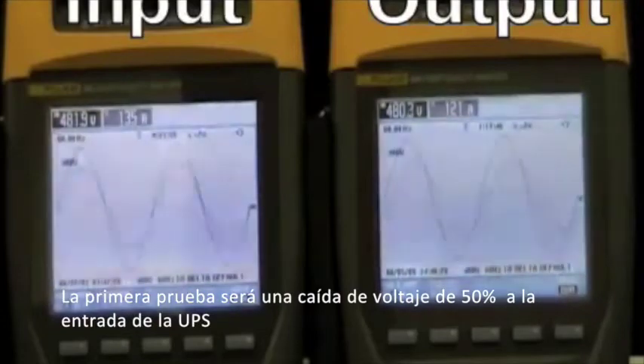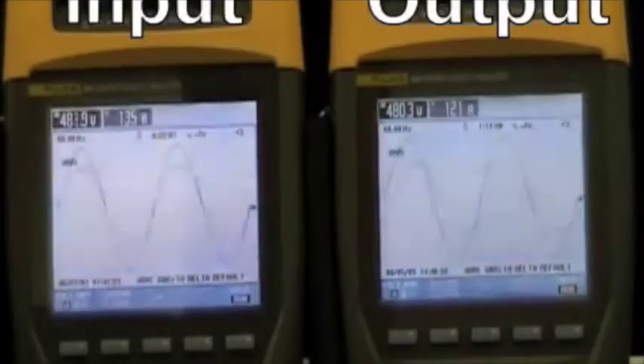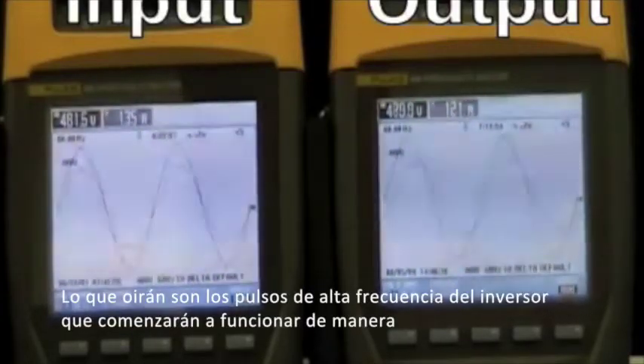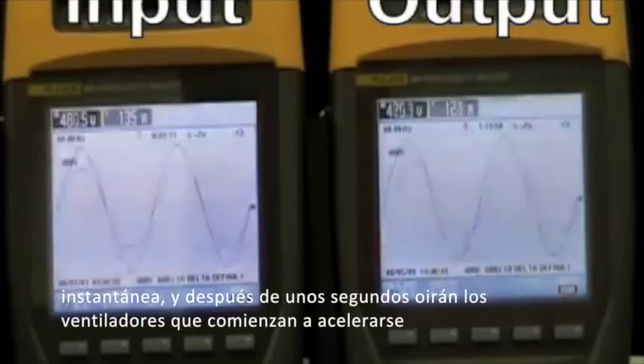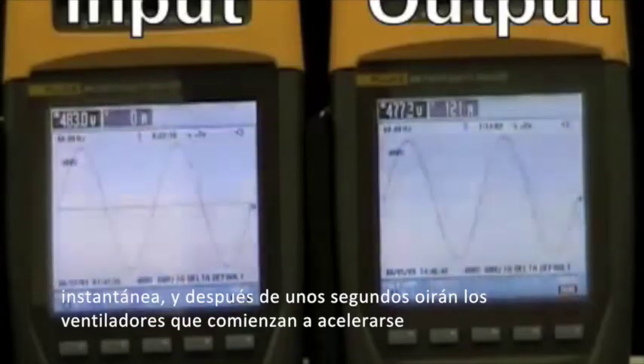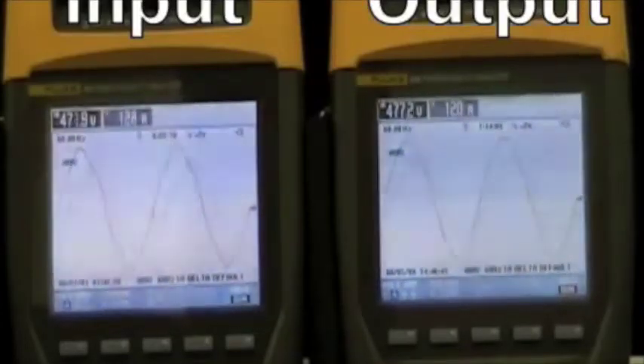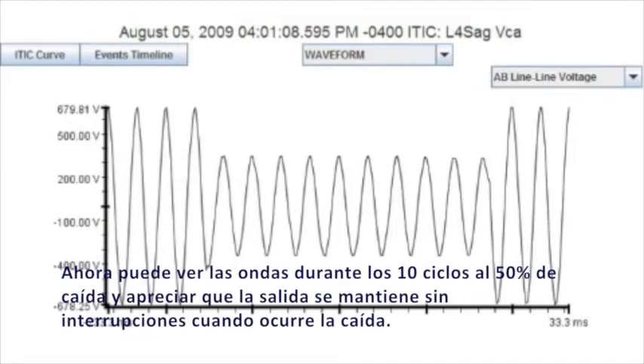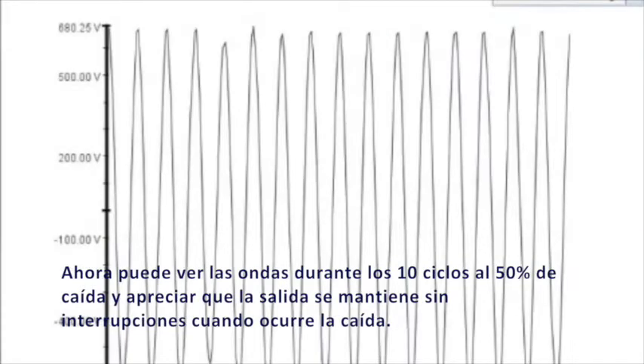Here, the first test will be a 50% sag of the input power to the UPS. What you will hear is immediately the high-pitched pulse width modulation frequency of the UPS inverter starts instantaneously, and then after a few seconds you hear the fans begin to spin up. Now you see the waveform showing the 10 cycle 50% sag, and the output is undisturbed where the sag occurred.